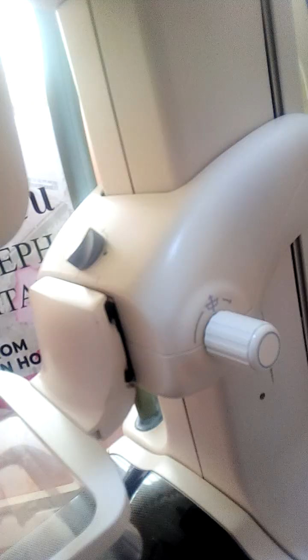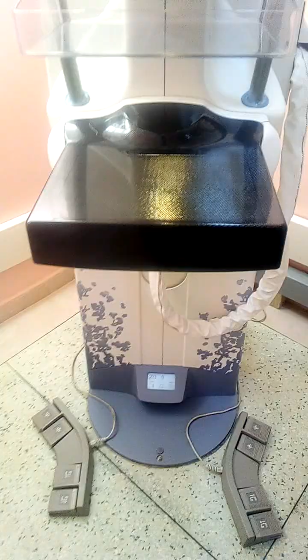Okay, and then now what you have down here is the screen for showing the angles. Once you have set to be able to give you the zero position. So it's going up. Okay, as you can see, it's now back to zero. That shows the gantry now is in a balanced position and ready for the images to be taken. So this is well set, very nice Mammo machine from the GE, and it is really a very good and simple machine to operate.